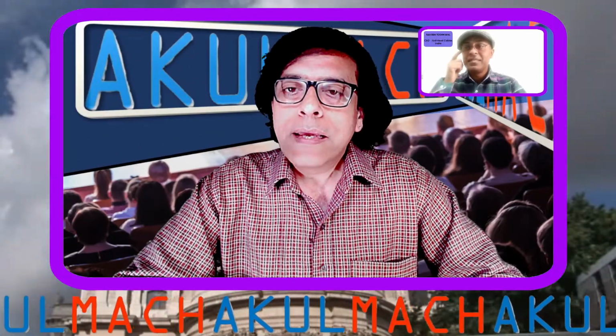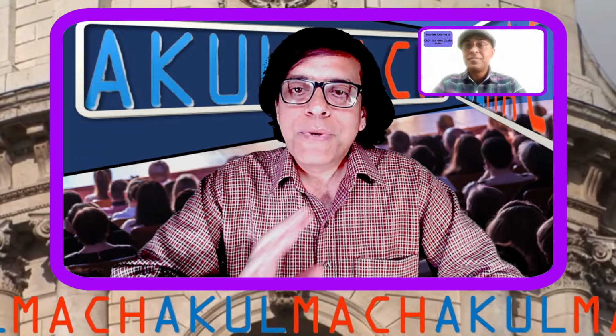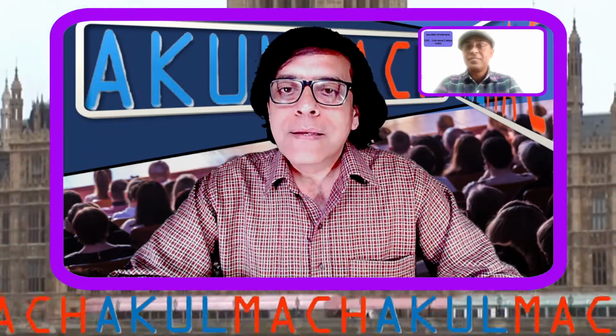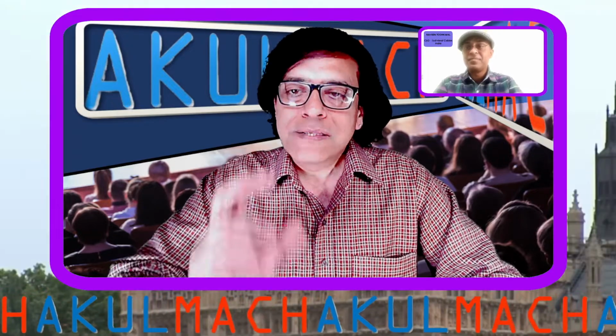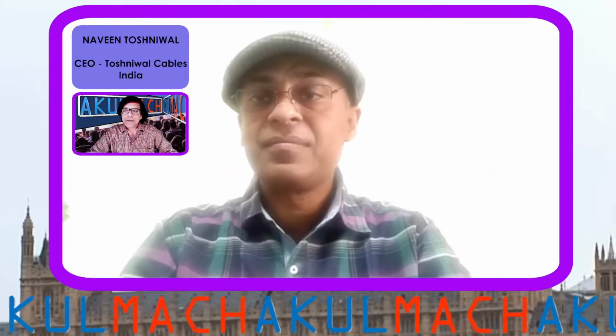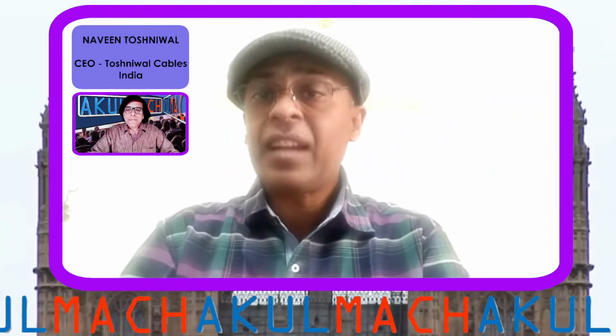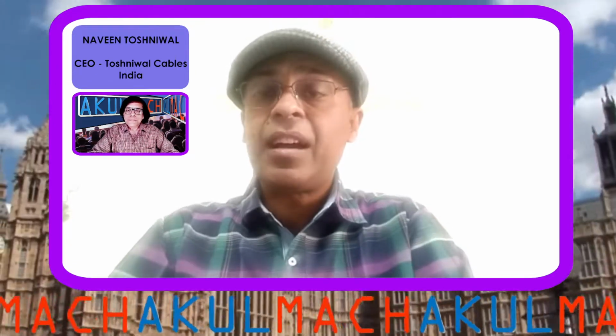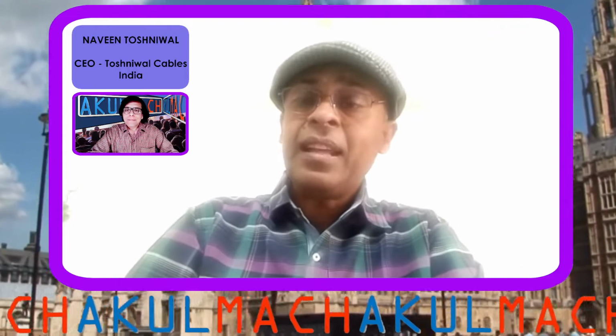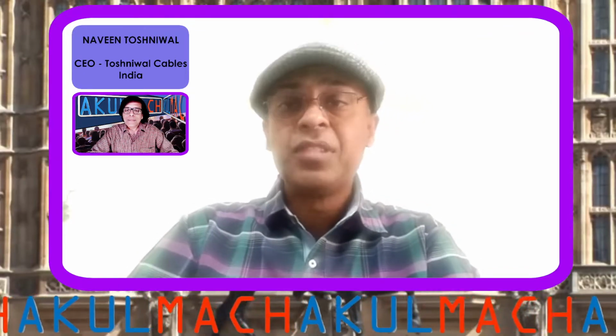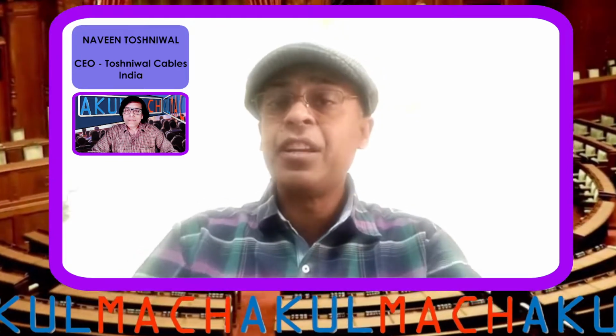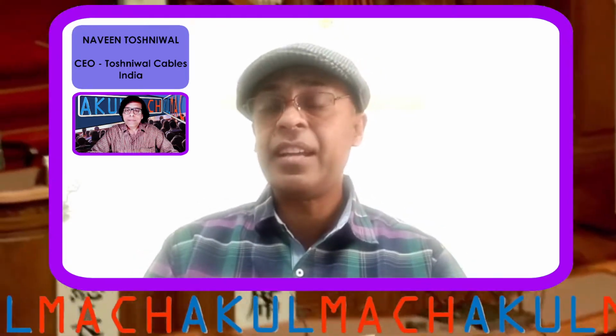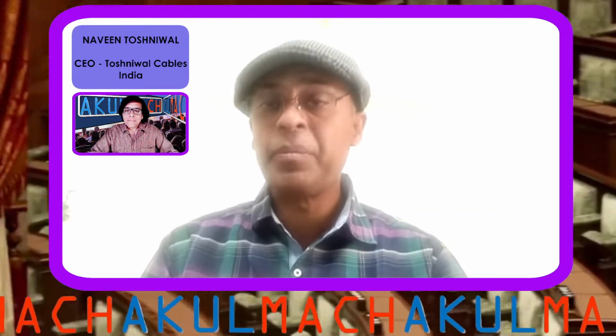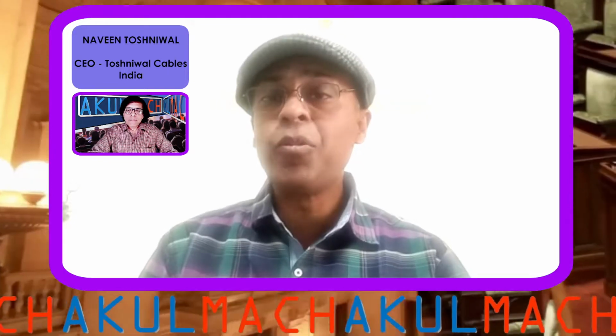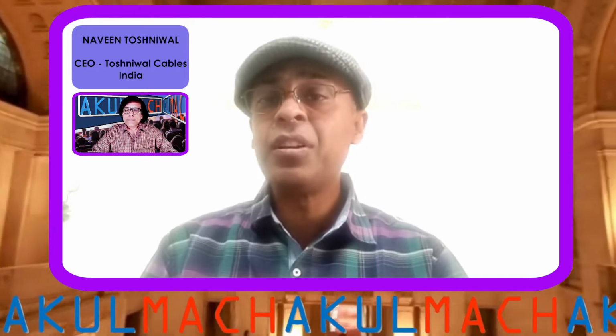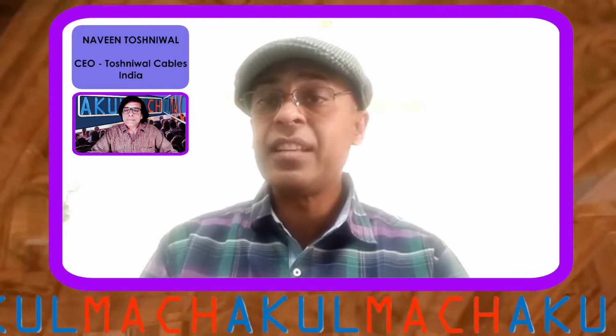And any industry can be using this. And you also mentioned the shielding. So again, is it very generic for all industries, or is it specific to only certain applications and industries? See, mostly we will recommend taking a shielding to avoid or reduce the electrostatic interference. But then again, it will be customer or end user specific. If they really require the shielding. If they don't have any power cables or any other interferences nearby, then shielding may not be required, but we will always recommend going in for the shielding so that it provides a very good signal when we are measuring the temperature through the RTDs.